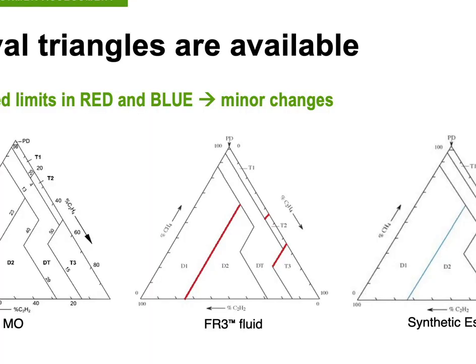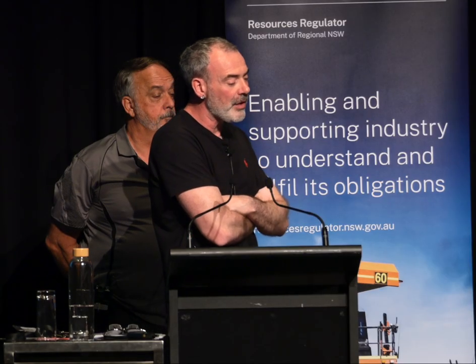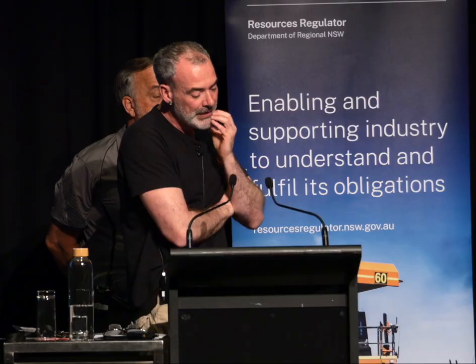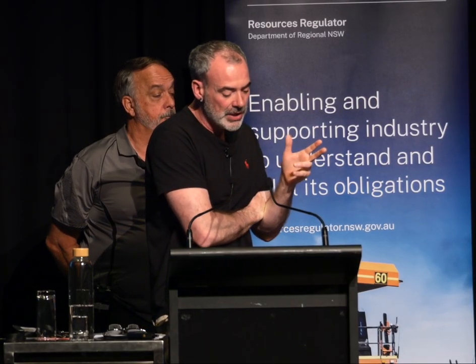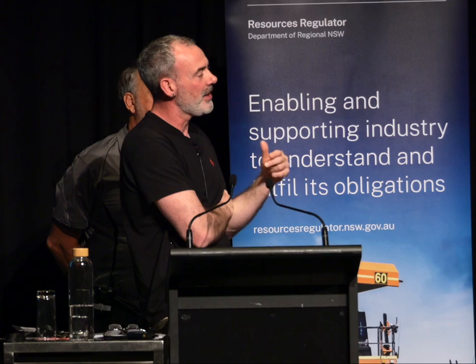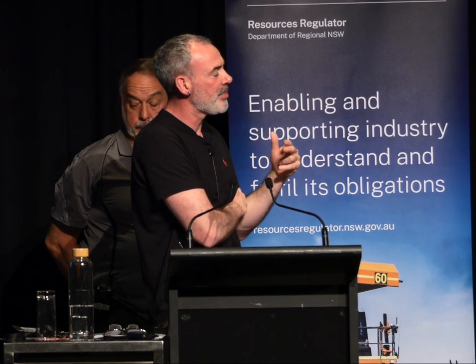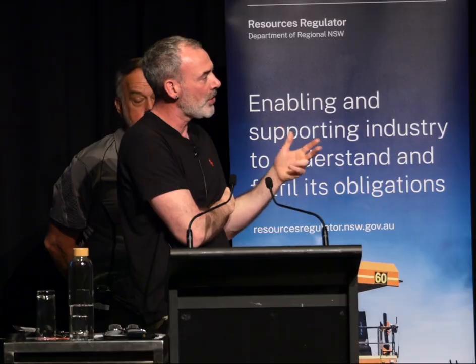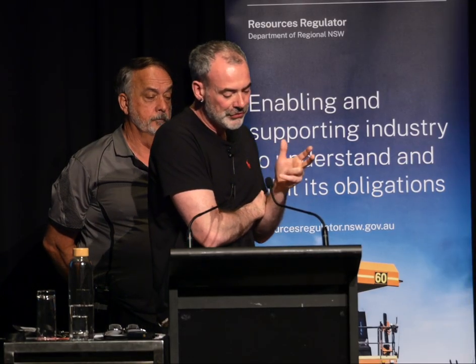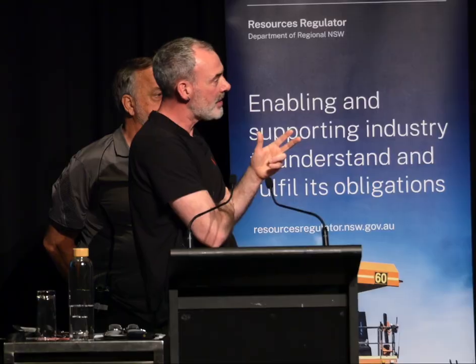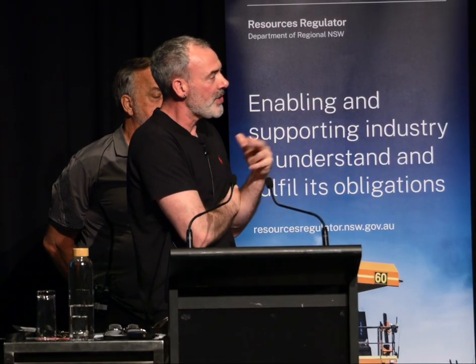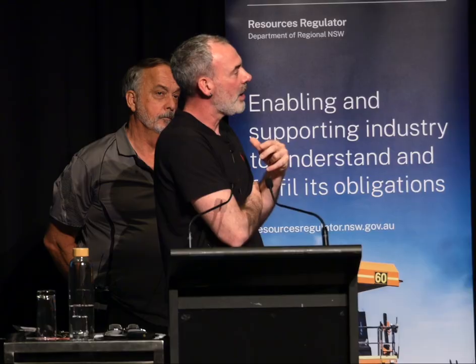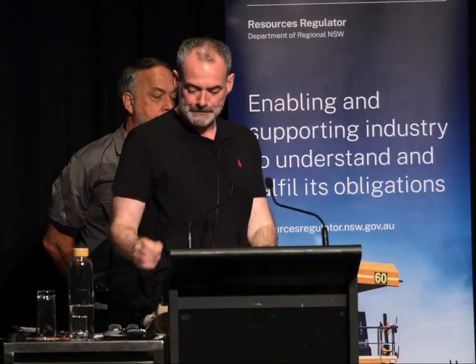So we've got Duval triangles, which are an analysis tool developed by Michel Duval from Hydro-Quebec in Canada. We can use Duval Triangle 3 for FR3. There's also one for synthetic ester. We can identify partial discharge, discharges of low energy, D1, high energy, D2, high temperature heating above 700 degrees Celsius, mid temperature heating, low temperature heating. And then we can use additional triangles 6 and 7 to help us further identify heating problems. And the question that these additional triangles can help us with is, is paper insulation involved in the fault? And it's more serious if it is.